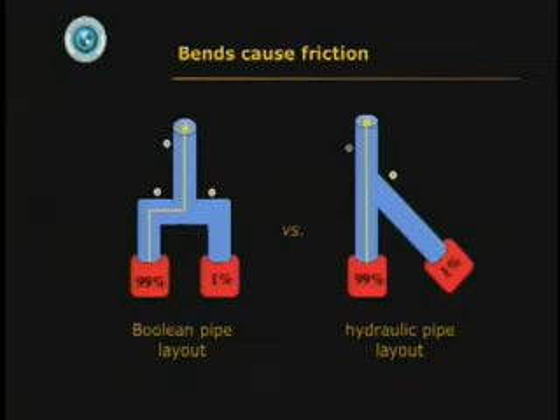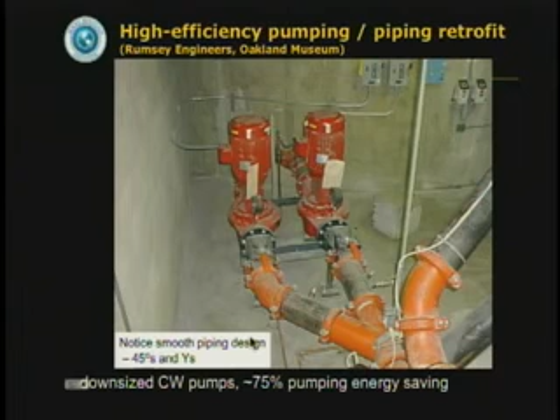Well, just because we never did it that way before. But Peter Rumsey did that at the Oakland Museum. Notice this Y joint, notice this sweet bend that then takes the pipe diagonally through the air, because Peter teaches pipe fitters to lay out supply pipes as if they were drains. There's another part of their brain that knows that if drains have right-angle bends, they'll clog. Right? So this is a really ugly and very lucrative pipe layout. It saved 3/4 of the pumping energy, and it got rid of 15 pumps that will never again waste energy in maintenance.